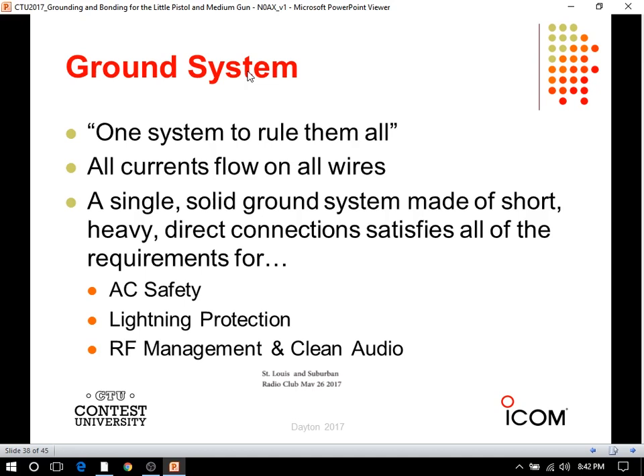Just remember, all currents flow on all wires. It's not like you've got a 60 hertz current that comes up to your ground system and says, wait a minute, I'm an AC current, I have to flow on the green wire, so I've got to go over here. It goes everywhere at once—Ohm's law is all that counts. Mr. Lightning will go anywhere and everywhere, RF will go anywhere and everywhere. So make sure all your wires are connected into this one system.